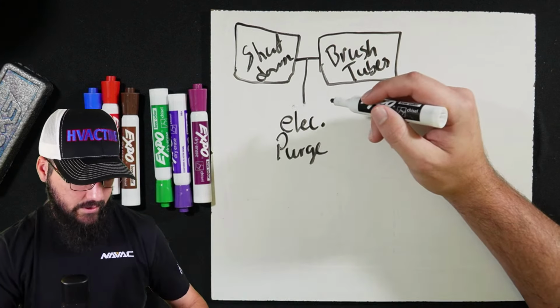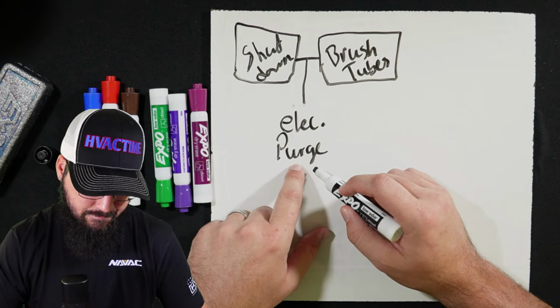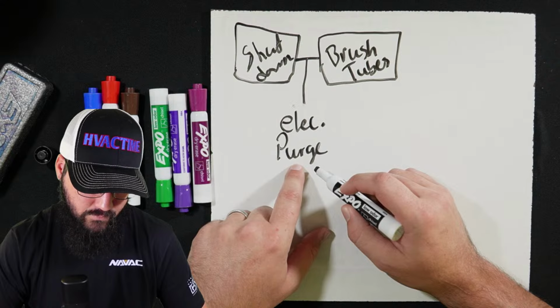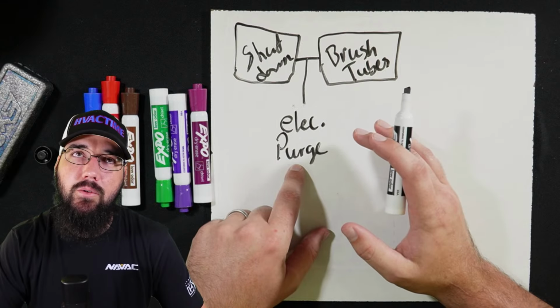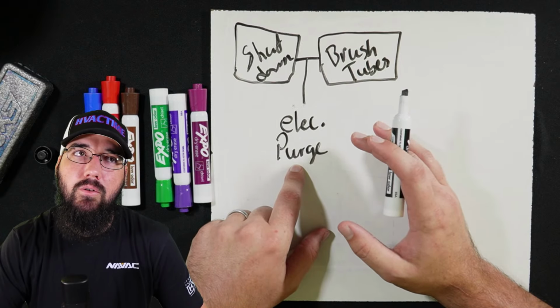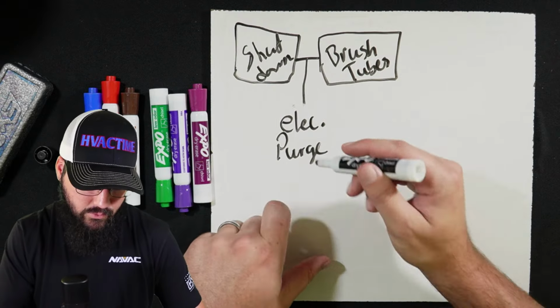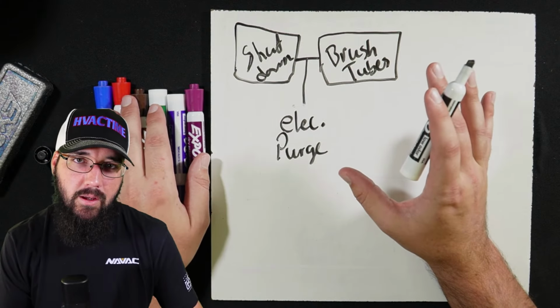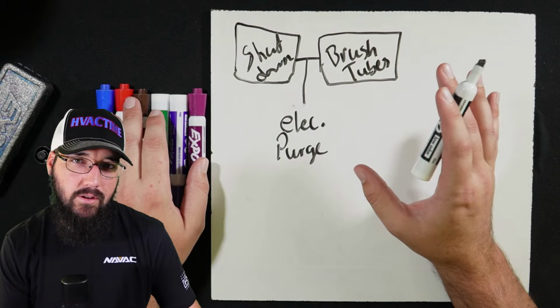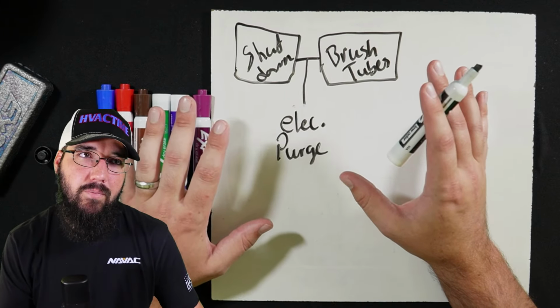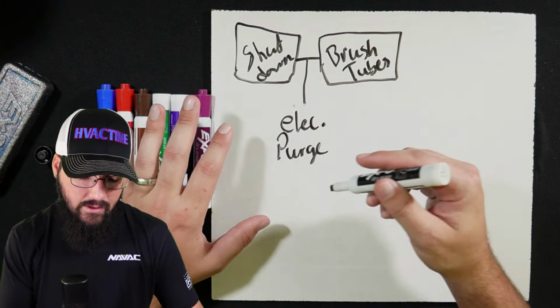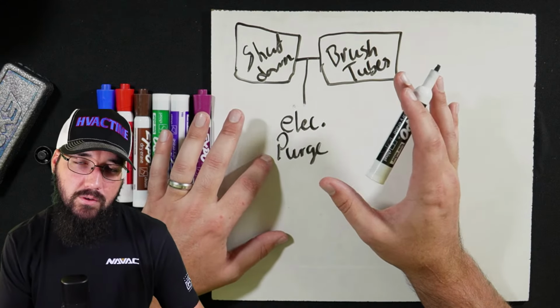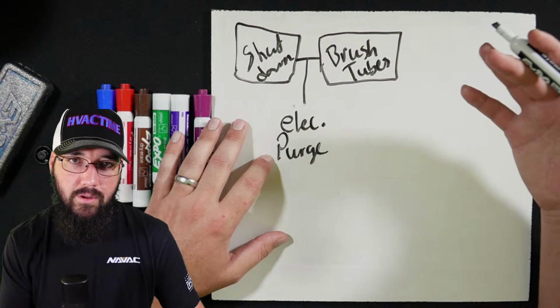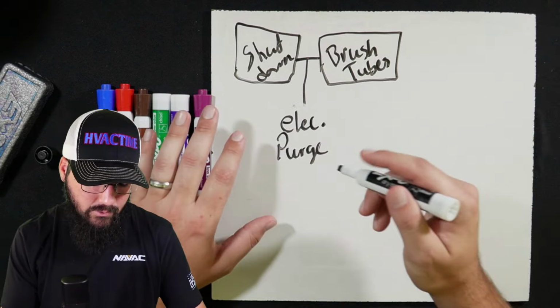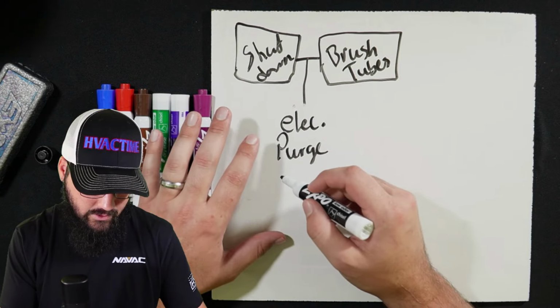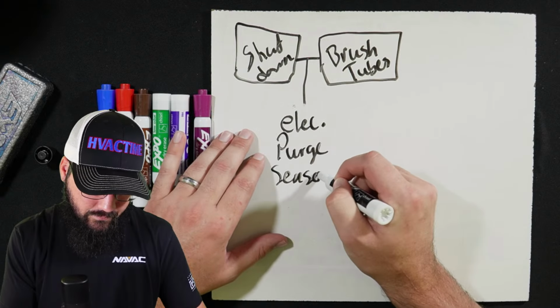With electrical checks, purge checks, and then let's see, what else would I have them do? We can verify sensors and stuff at the same time. While it's not ideal, most of the time it is best to verify sensors at operating temperatures. I've found that in most scenarios it's actually okay. If there's a major issue with a sensor, we can check it at standing and we'll call it good enough, right? So we could debate that ad nauseam if we wanted. Anyway, checking sensors.